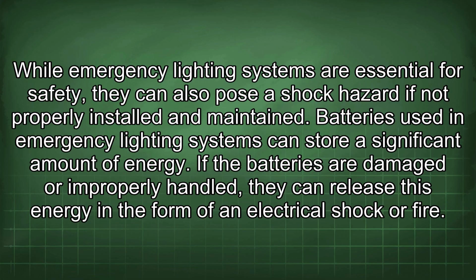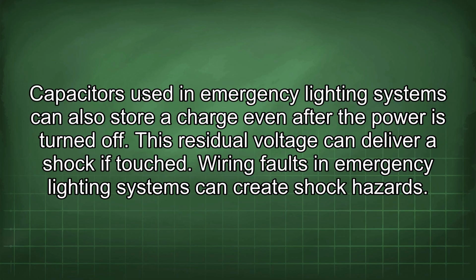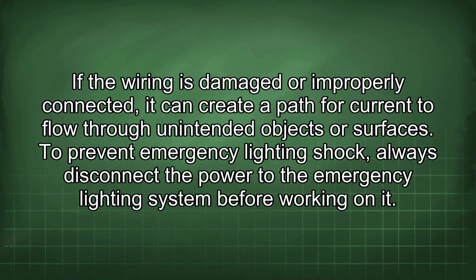If the batteries are damaged or improperly handled, they can release this energy in the form of an electrical shock or fire. Capacitors used in emergency lighting systems can also store charge even after the power is turned off. This residual voltage can deliver a shock if touched. Wiring faults in emergency lighting systems can create shock hazards. If the wiring is damaged or improperly connected, it can create a path for current to flow through unintended objects or surfaces. To prevent emergency lighting shock, always disconnect the power to the emergency lighting system before working on it.